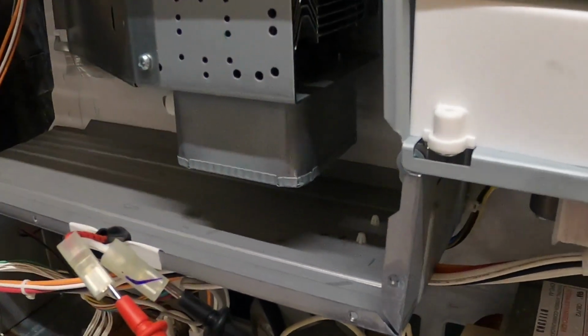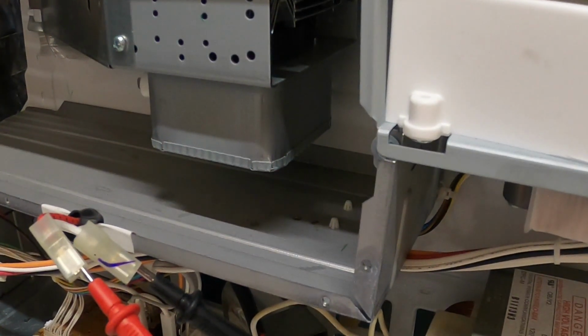So at this point, you know you have 3 volts AC filament voltage. At this point, the problem is 99.9% likely to be your magnetron tube. So I'm going to drop the magnetron out, and I'm going to show you something you need to check for. I have seen it on this model 5 or 6 times, but I've seen it on all microwaves over the years. You can have a bad magnetron to the point where the unit's not repairable, but I want to show you that.